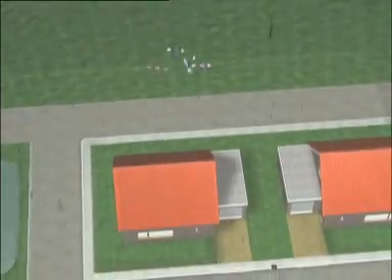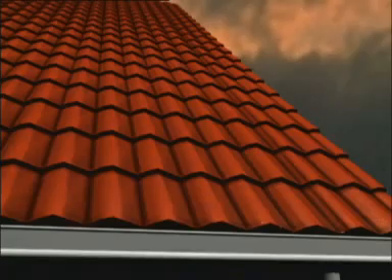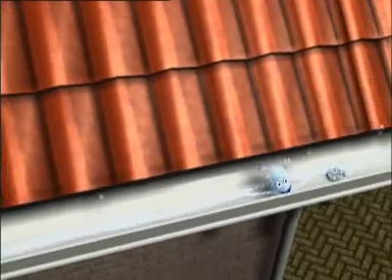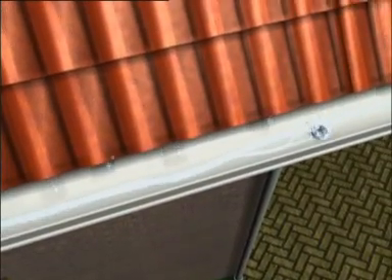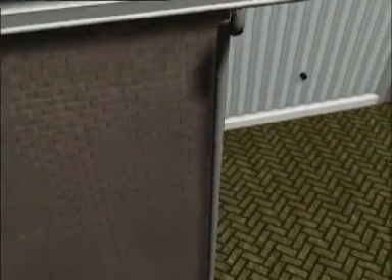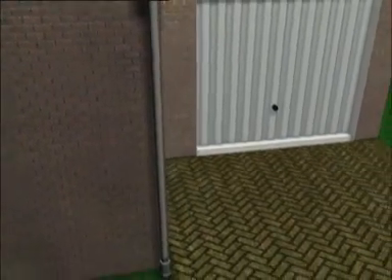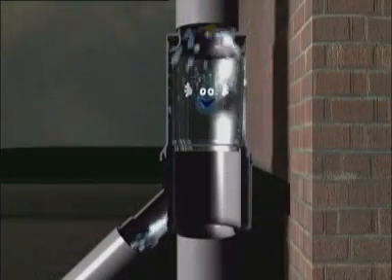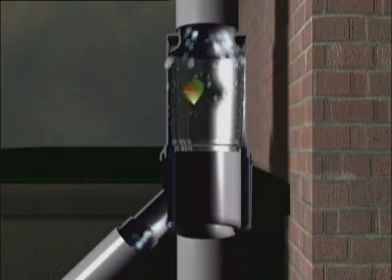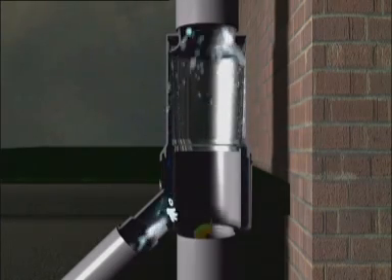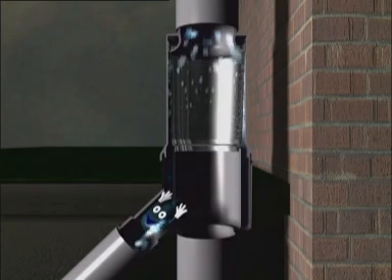In the Netherlands, the annual rainfall on a roof of 100 square meters is approximately 80,000 liters. The cleanliness of the rainwater is determined by the surface of the roof. Each drain pipe is fitted with a filter that filters the rainwater to 400 microns. As the water clings to the inside of the pipe, approximately 95% of the rainwater is drawn through a filter.